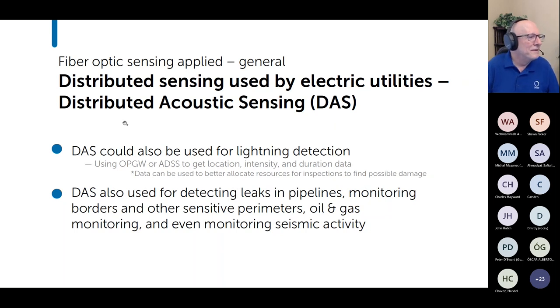So continuing with distributed acoustic sensing. You could also use it for lightning detection. You'll see we've done some testing on that that we'll talk about later in this presentation. So you could use OPGW or ADSS to get location, intensity, and duration data. And then in turn, that can be used by utilities to better allocate resources for inspections, right? Because right now, you would go inspect the line once every year or two, or maybe even more, and you send out a guy and he's going to look all along the line. But if you were gathering lightning data, you would know, okay, we had a strike here. Let's go check that area. And that can give you a more efficient use of your inspector's time to be looking for specific problems at specific locations, as opposed to just a general inspection.